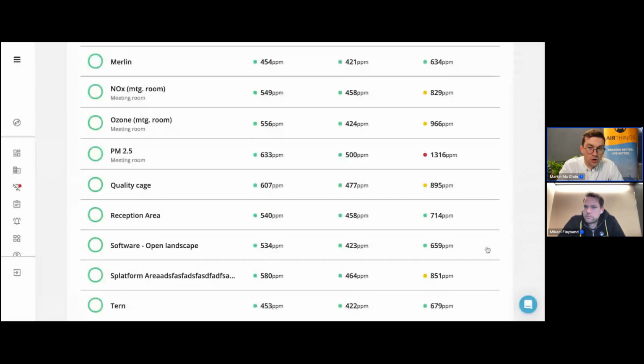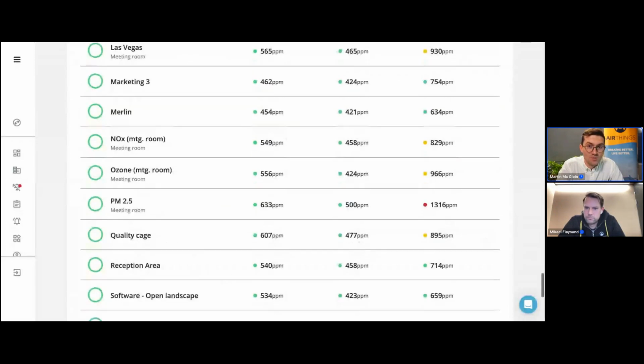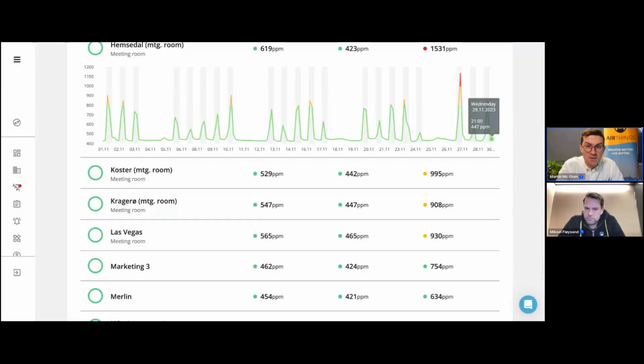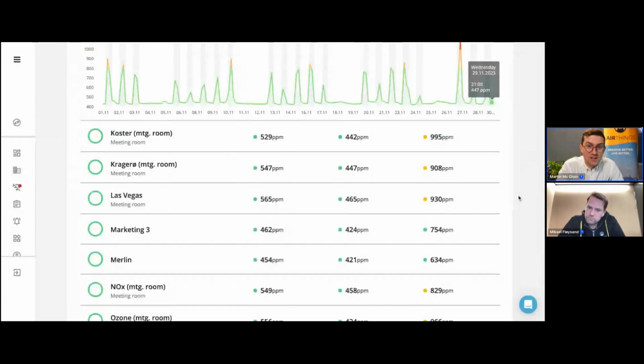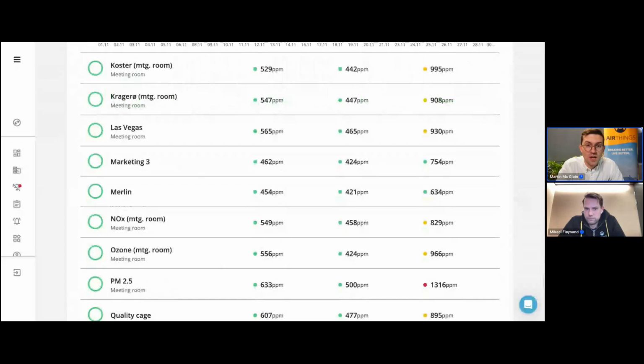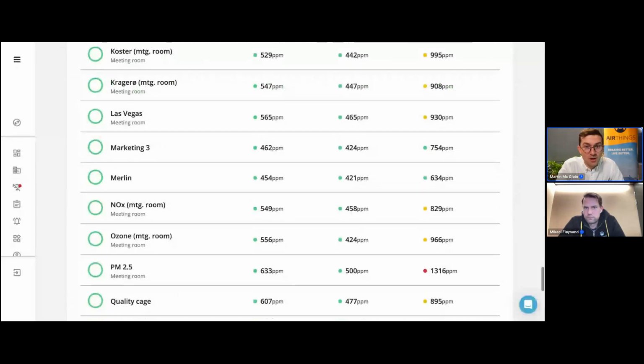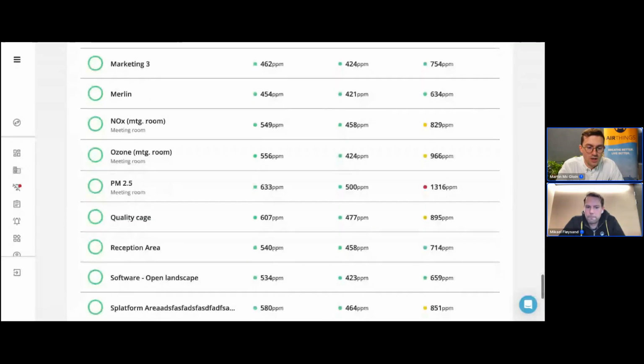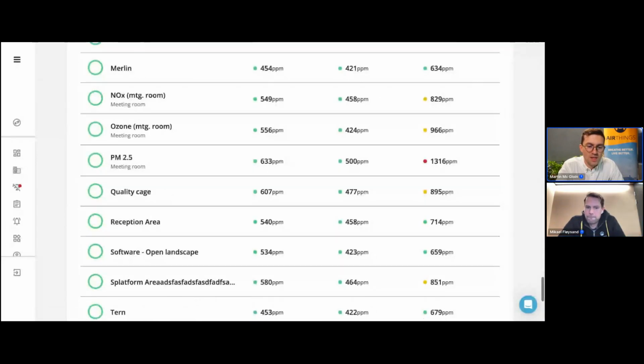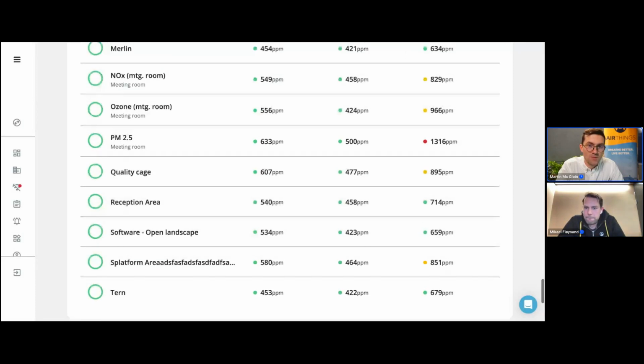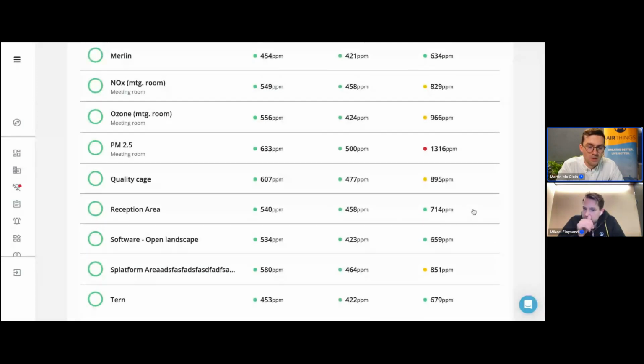And it's also worth noting, which I assume most of this audience might be familiar with, that the lowest CO2 measurements are around 400 ppm, and that's really the lowest you will physically be able to go due to atmospheric CO2. The presence of CO2 in the air is, well, it's still rising, but around 420 ppm at the moment. So if you have too many greens in the highest range, it's an indicator that there might be some over-ventilation going on and an opportunity to optimize.